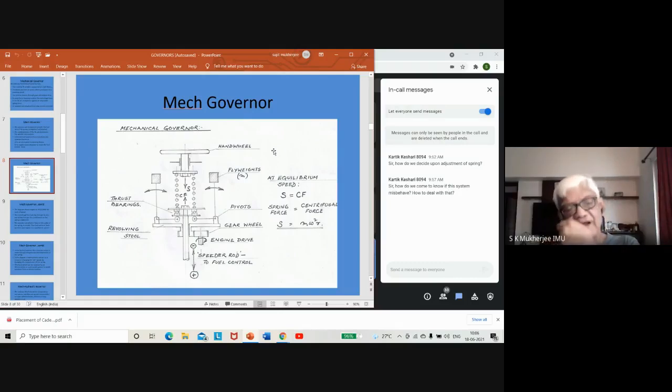All right. The governor gets an electrical signal, much like the governor also gets the desired value as an electrical signal. It has a potentiometer or electrical devices. And then it gives an output to an electric motor. That electric motor will run a shaft which will have a bevel gear and an arrangement to turn this spindle here. That is purely mechanical. So the mechanical movement of this will compress the spring. There is no electrical part over here.